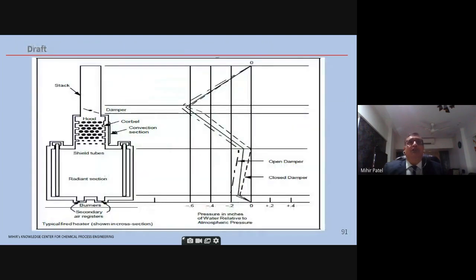Now draft. Draft is very important in a fire heater. Draft is basically a negative pressure which is kept inside the entire fire heater. Now why is it kept negative? There are two reasons for this. The first reason is the casing of the fire heater is always made from construction steel to keep the cost down. Now suppose the inside of the fire heater is kept at a positive pressure.